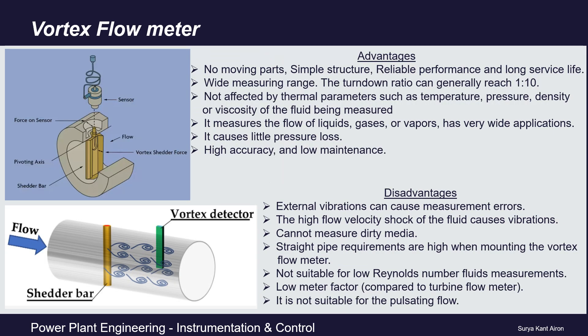Vortex flow meters use an obstruction — called a bluff bar — placed in the fluid flow path to generate vortices. A detector is installed to measure the vortices generated due to the presence of this obstruction. The number of vortices generated are directly proportional to the fluid velocity and thus to the fluid flow rate.